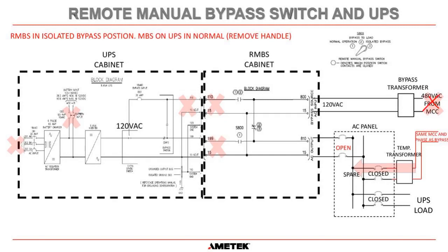So, and as you can see here, we still have the bypass isolated to the UPS. And the other thing that I want to show you is what we tend to do within AMETEK Solid State Controls is we try and keep the wire numbers the same. So you can see here that you should connect terminal 110 in the RMBS cabinet to terminal 110 in the UPS. 15 is neutral. And then the output of the UPS is 199. That should be connected to 199 in the UPS. Obviously, 15 is neutral. The only thing that we don't know is what you've called your wire numbers going from the bypass transformer here into your UPS. But your bypass source input should be connected to 800. And then the output of your RMBS to your critical loads should be connected to 810 and 15. Okay.